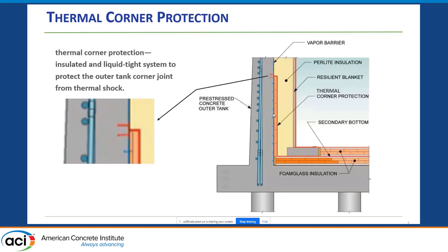The thermal corner protection — at least the definition of it in the code — is an insulated and liquid-tight system to protect the outer tank corner joint from thermal shock. As Ralph indicated, that applies to a monolithic joint between the concrete slab and the concrete wall. The thermal corner protection and secondary bottom consists of the horizontal embed, the horizontal plate and vertical plate, and finally the secondary bottom — along with the insulation behind that — to protect this joint during a spill condition in the annular space.